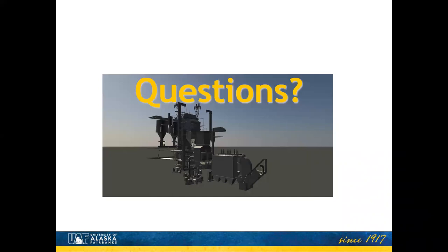Hey, Mike and Doug, in redoing the plant, or the original plant, what was lost from the original plan by downsizing? Probably the most significant thing is originally we were aiming for two smaller capacity boilers that would allow them to run one at its best efficiency point all the time for the next several years while demand increased. Having two boilers doubles the amount of support equipment that goes with them, so that was a big cost driver. Instead of two small boilers, we had one large one. That was the biggest change we had during rescoping.